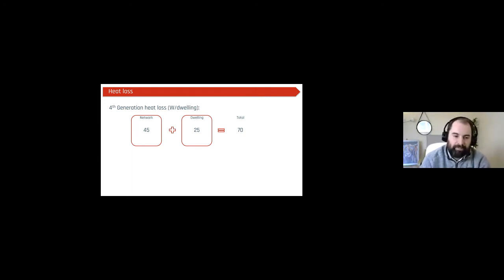So heat loss. For fourth generation systems, these numbers are in watts per dwelling, instantaneous heat loss. We typically see for a well-designed, good performing fourth generation heat network about 45 watts per dwelling in the network, and about 25 watts per dwelling within the HIU. The 25 watts can be reduced if you do some clever things with standby modes and keeping temperatures warm away from the dwellings. But as a general approach, this is fairly standard. So you're looking at about 70 watts per dwelling of heat loss.